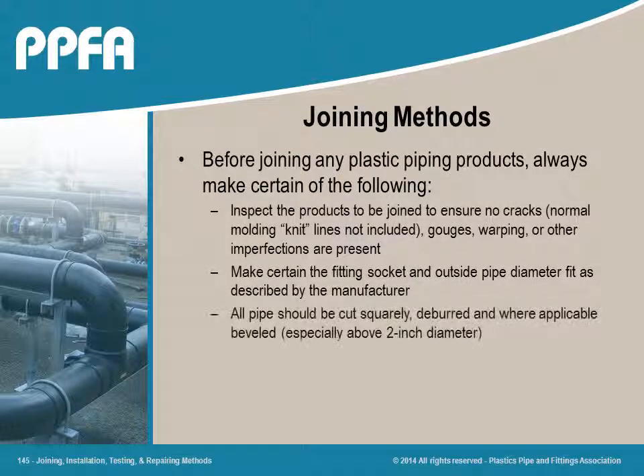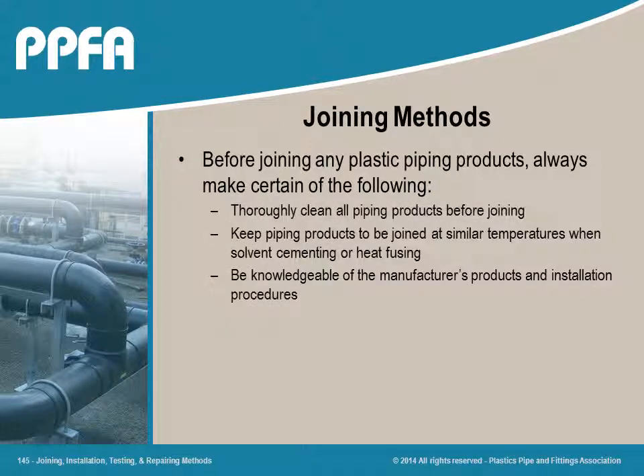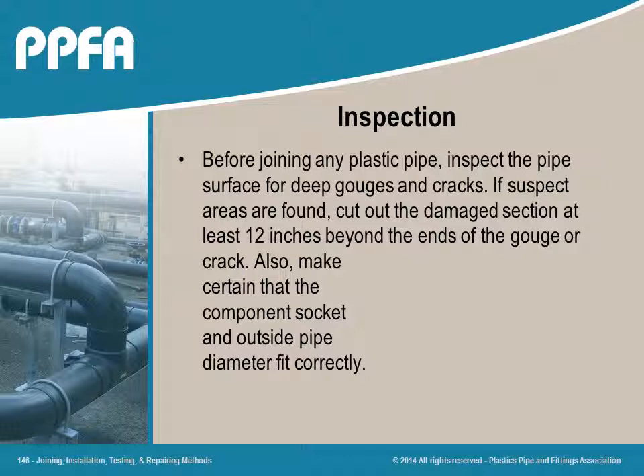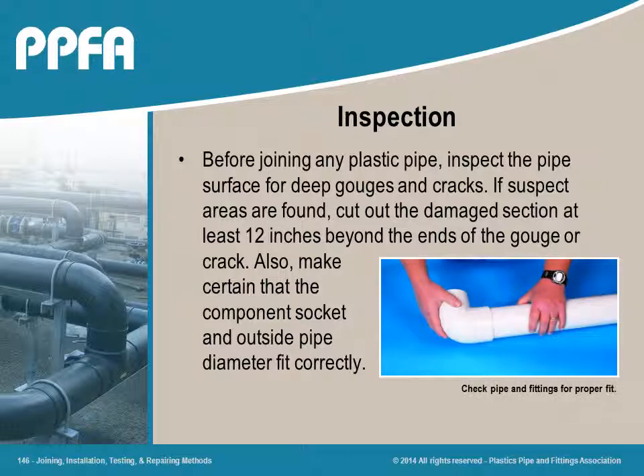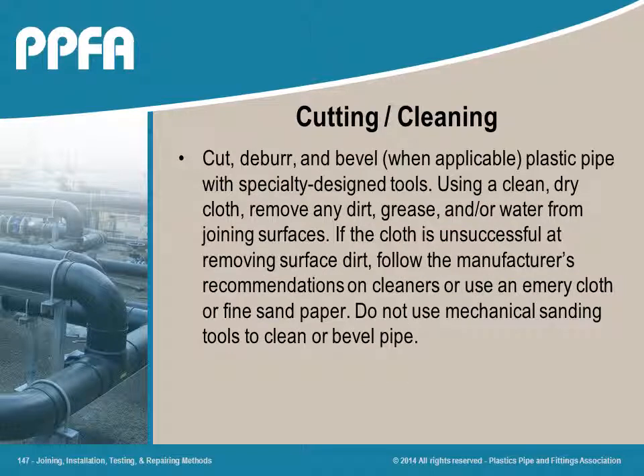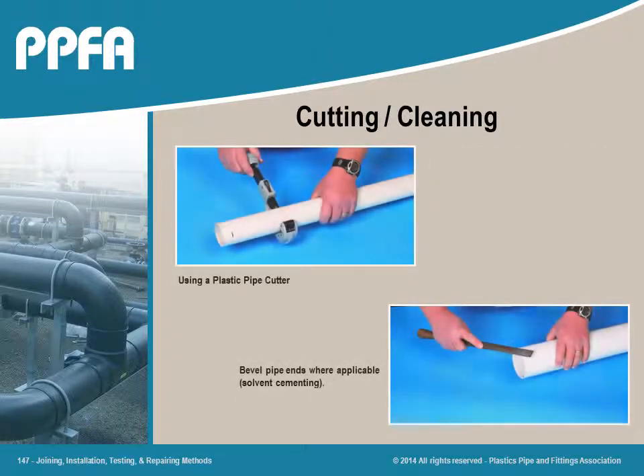Before installation, all piping materials must be thoroughly inspected and cleaned. When cutting plastic pipe, use the proper tools and deburr the pipe ends, especially when joining solvent cemented and heat fused pipe into socket fittings and valves. It is important when joining plastic pipe: 1. To keep dirt and grime from the joining products. 2. Keep products to be joined at similar temperatures before joining. And 3. Follow completely the manufacturer's joining instructions. Before installation, all piping products should be thoroughly inspected for cracks or gouges. If these irregularities exist, remove the damaged parts completely.